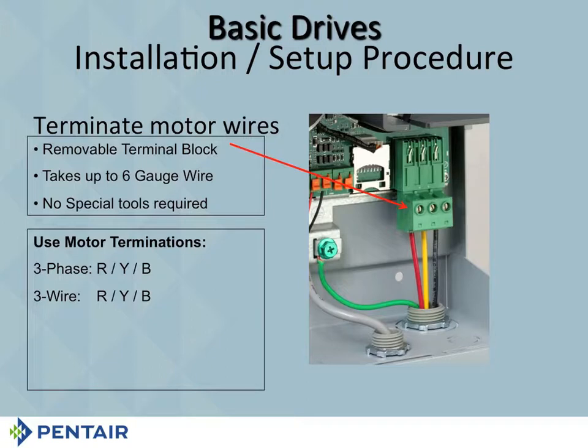If you're doing single phase out 3-wire, same thing: red, yellow, black. Now, of course, remember, the drive knows you're doing single phase, so it's going to change the amperage coming out. On 3-phase, red, yellow, and black are each going to get the same amps. On single phase, red and black get different amperage than yellow. And so you got to understand that, all right? If you're going to do 2-wire, this is where it gets a little different, because with 2-wire, you're only going to use yellow and black. Even though the 2 wires might be black and black, or the 2 wires might be red and black, you're going to use yellow and black. On single phase, the red wire is equivalent to that starting capacitor, running capacitor. It's in the cap start, cap run control box. And on a 2-wire motor, we don't have a running capacitor, so we don't even use it. So if you don't hook up to yellow and black, it's going to fault out on you.